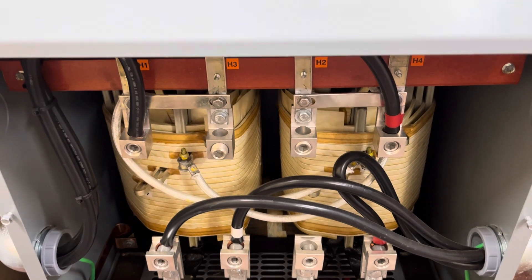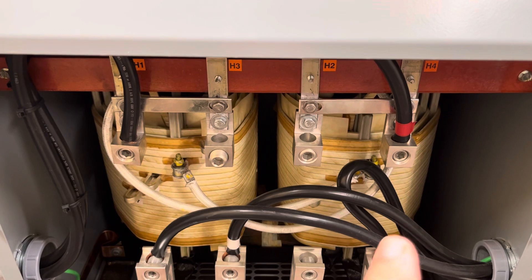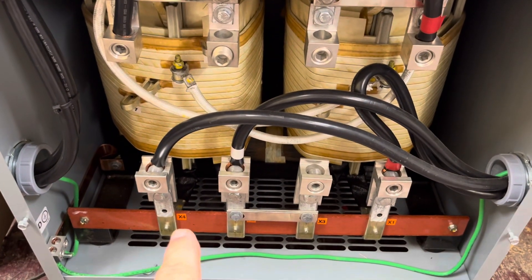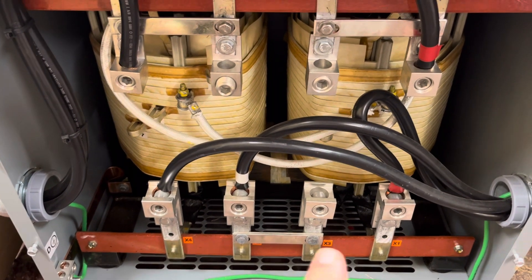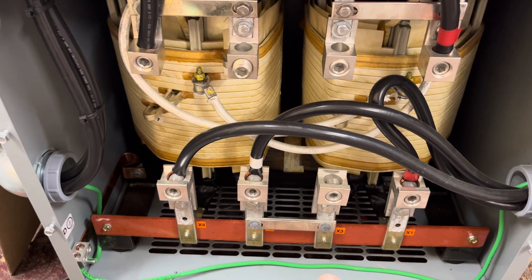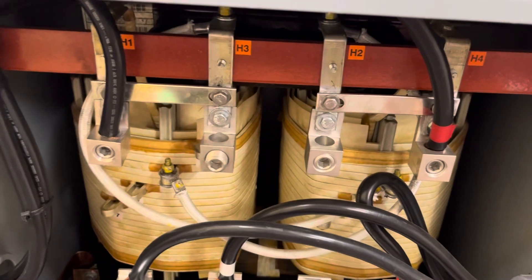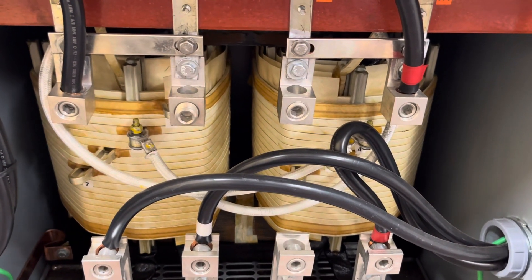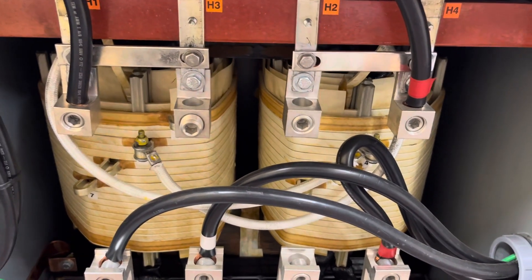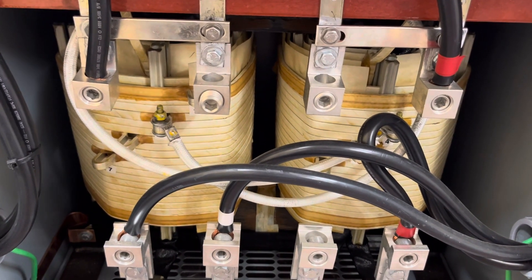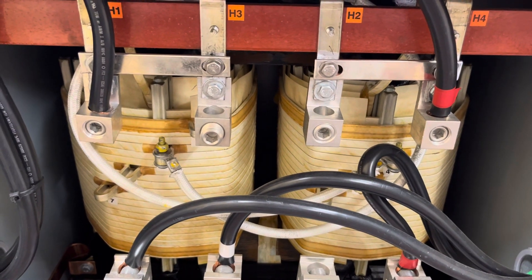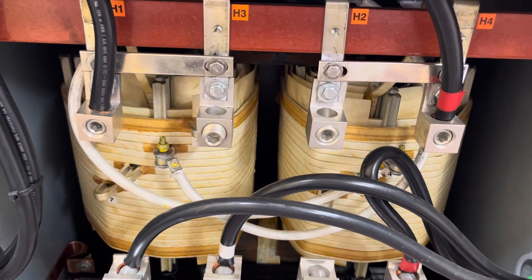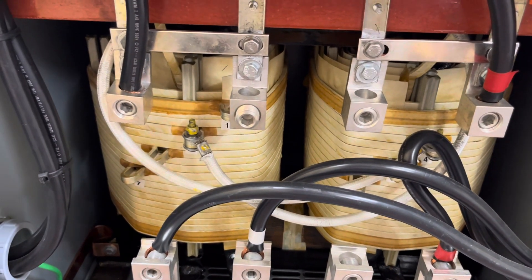And what that means is this winding can be configured for 480 volts or 240 volts. And the secondary can be configured for 120 or 240 or split phase 120-240, which is the way I have this set up. Basically, what you have in this transformer are two sets of windings on the primary side. There are two 240 volt windings that can be connected in series, so you can connect 480 volts to the primary, or they can be connected in parallel, so you can connect 240 volts on the primary, which is what I've done.